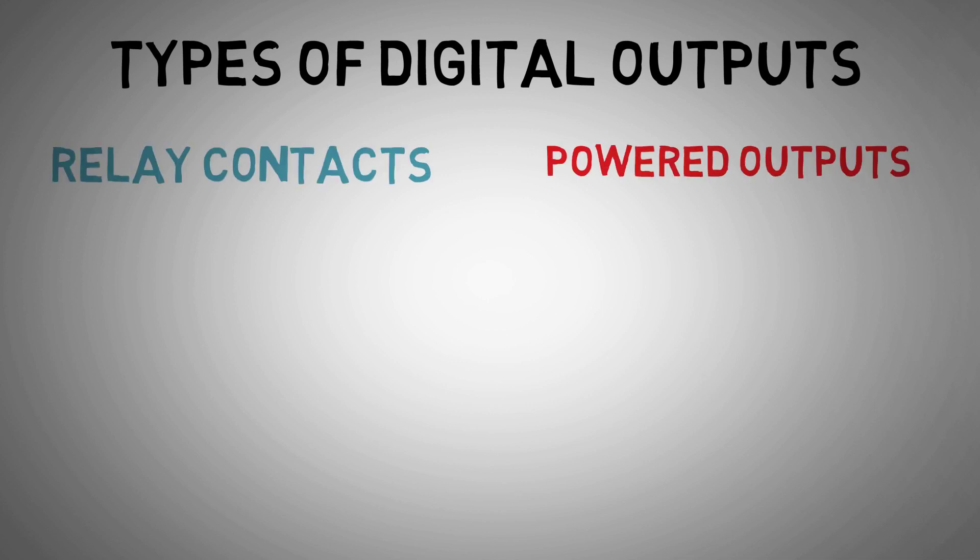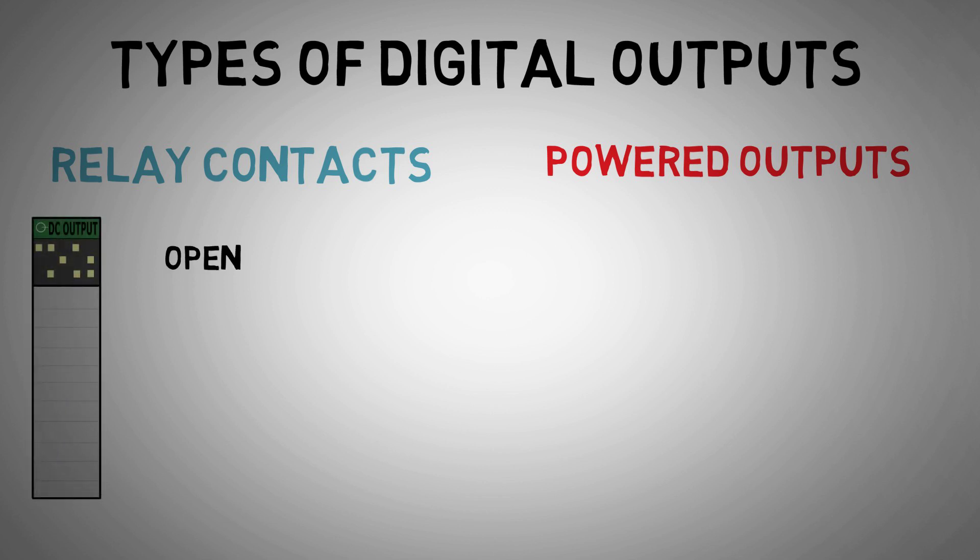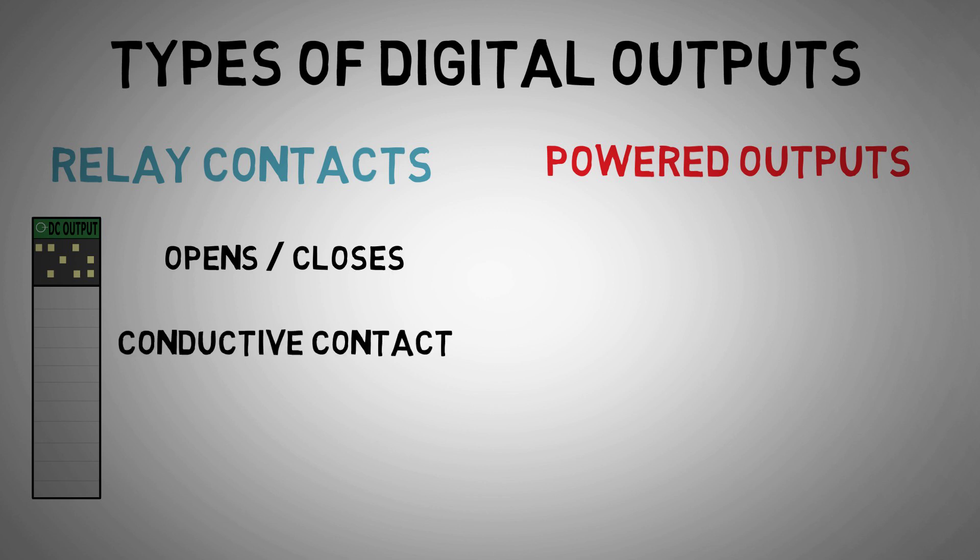With relay contacts, when the PLC processor signals to change the digital output state, the output card closes a relay-like contact that provides a conductive path to another circuit. This is called a dry contact, where no voltage is produced by the contacts and power comes from the separate circuit.